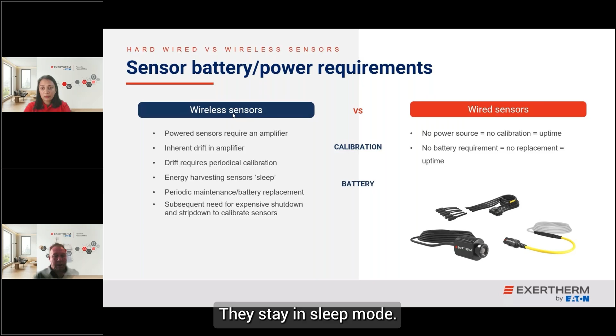Wireless sensors, if they're using the signal or the energy from the actual bus bar itself, so the magnetic field, those sensors can go to sleep. If you de-energize the board, you de-energize that piece of switchgear, the sensor will sleep because there's no power to actually make it operate. Those sensors, when you re-energize, don't always come back to life. They stay in sleep mode. If they're in sleep mode, they need replacing. So now you've got an instance where you're having to have an outage, you're having to have downtime, getting inside the gear to replace sensors.